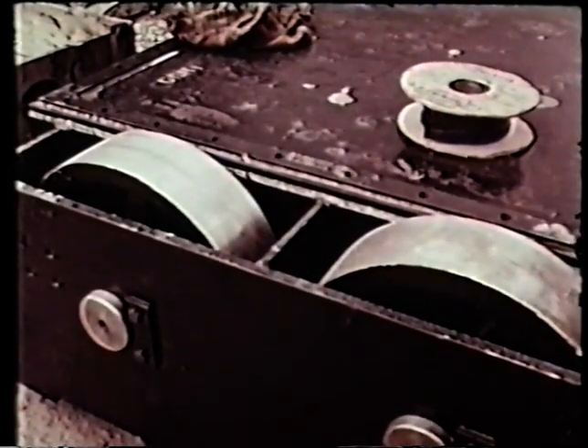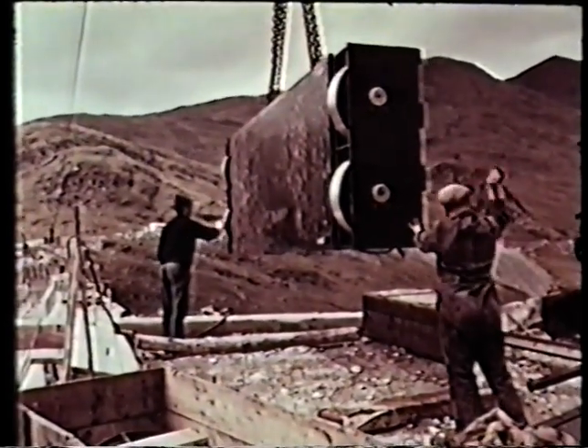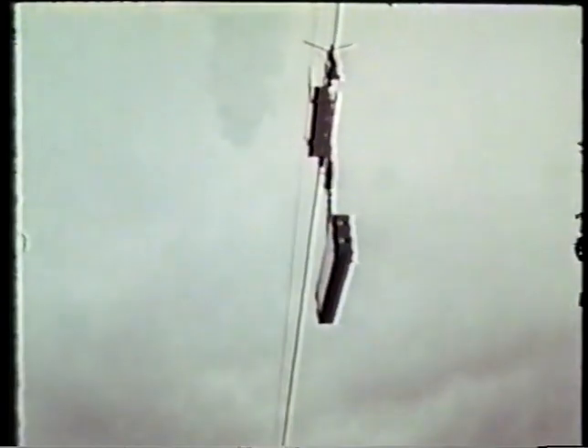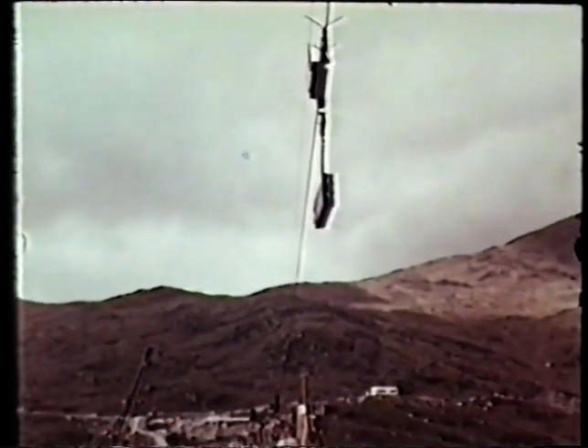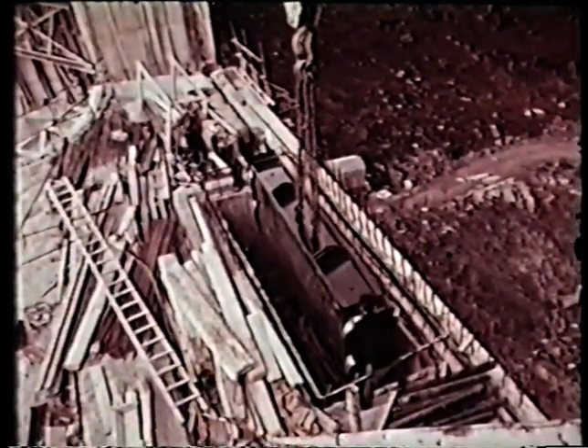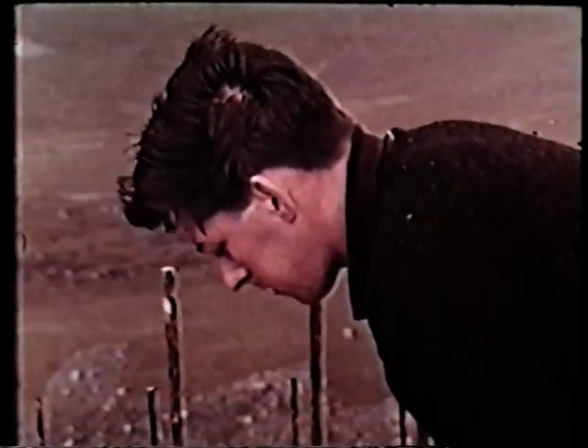The control gates, built up in sections, besides the normal function of withstanding the static head of the reservoir, are required to withstand on the other side the maximum pumping head. They are also required to close by gravity against the maximum flow from the reservoir, and to be incapable of closing to more than three-quarters shut against the maximum pumping flow to the reservoir. The profile of the gates ensures that the hydraulic loads will be the optimum to assist gravity closure and positive seating under conditions of maximum head and flow from the reservoir.